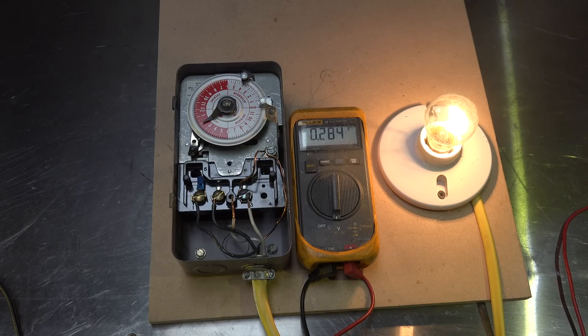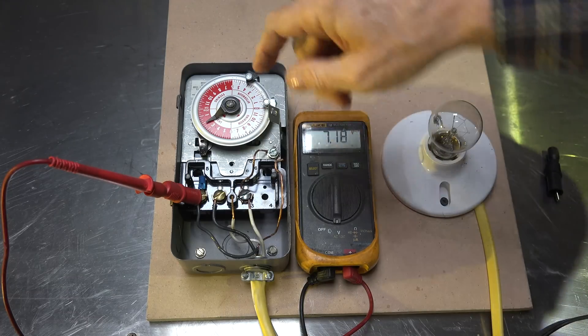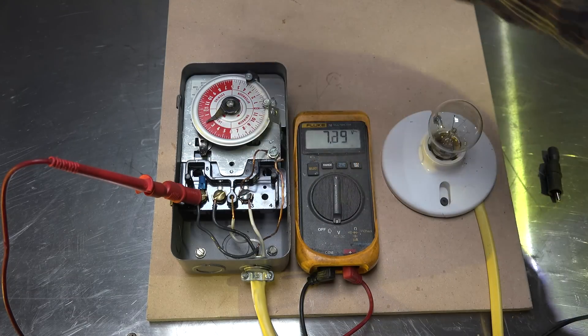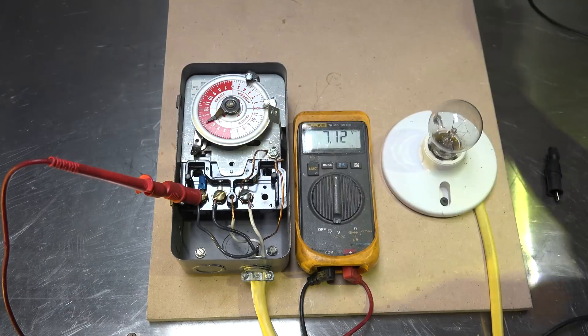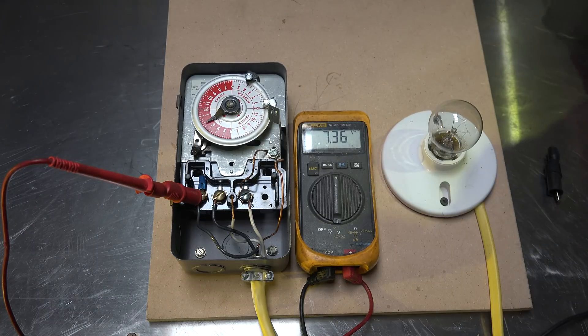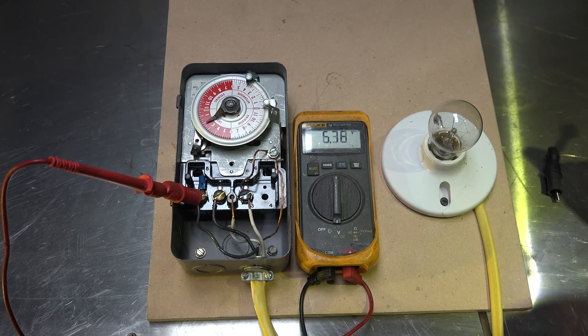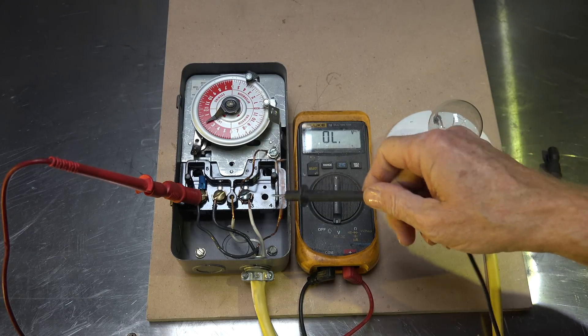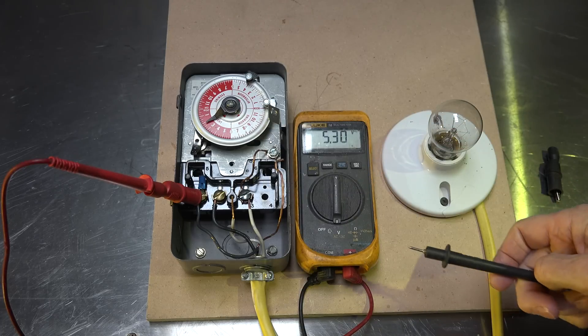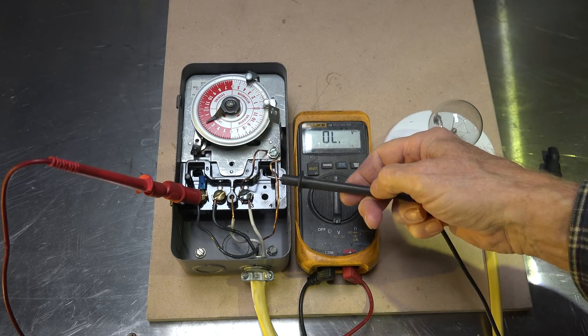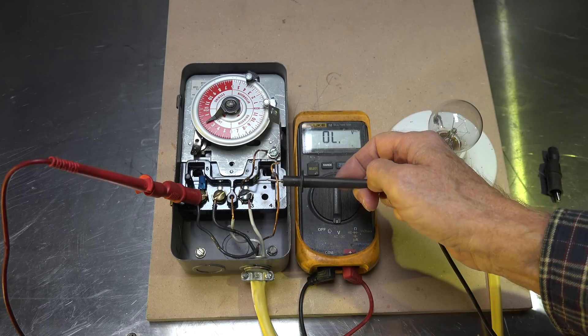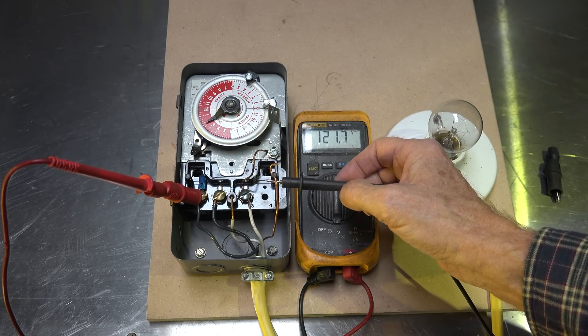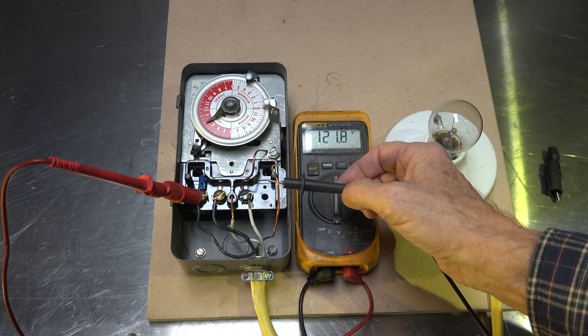So I'm gonna go a little farther on this and see if I can come up with why this is so bad. Now I've disconnected this ground wire right here and we go to turn it on. Okay, it doesn't come on because the power was going through this ground wire. And if I put my probe between the hot lead and the ground, I get power.